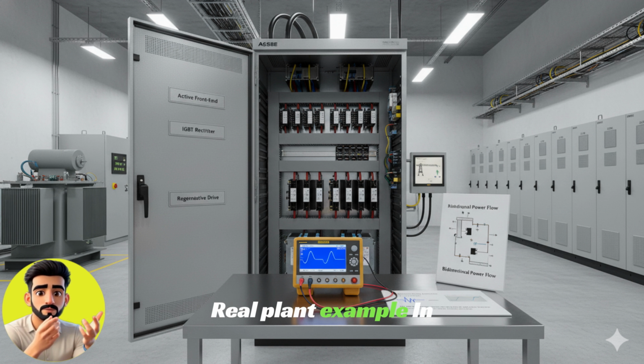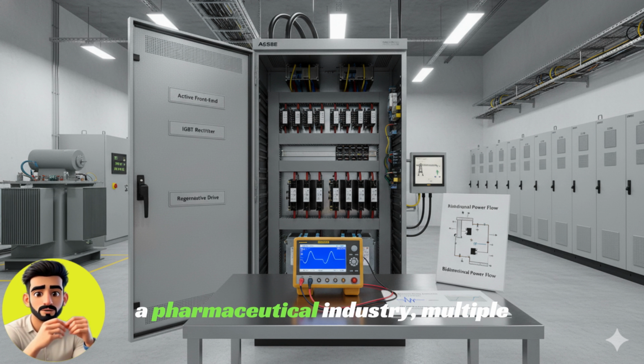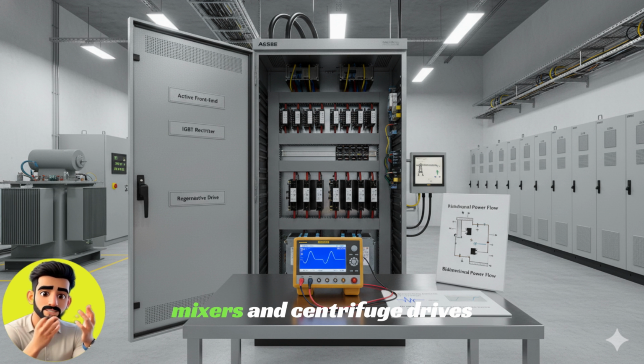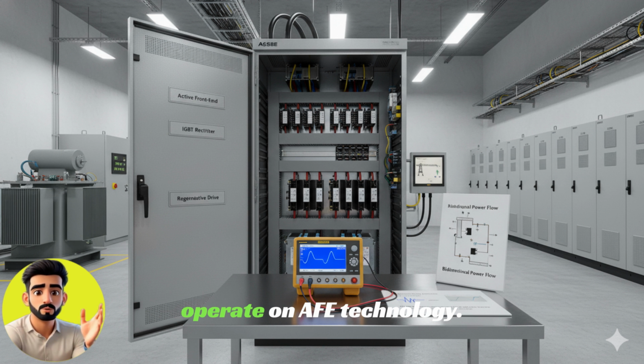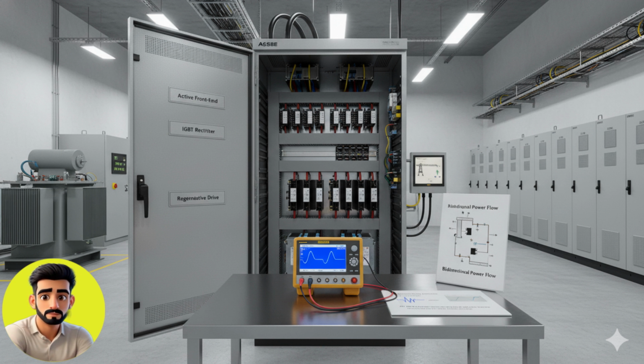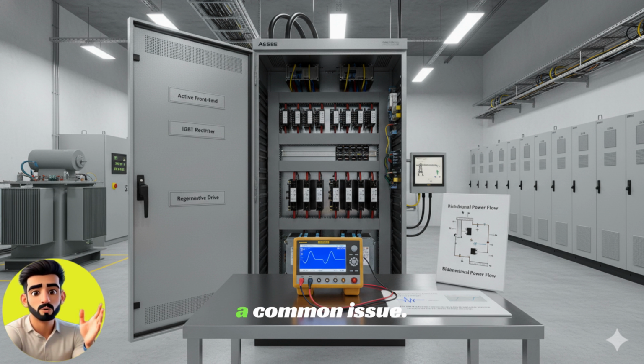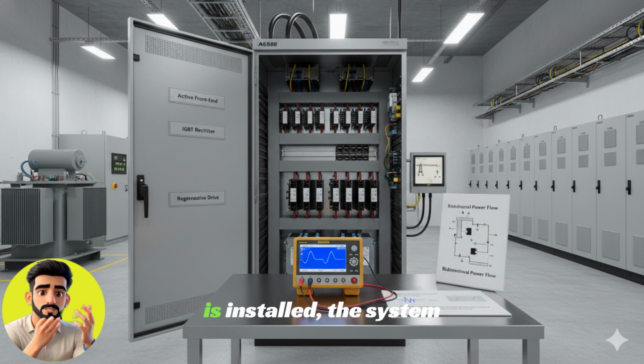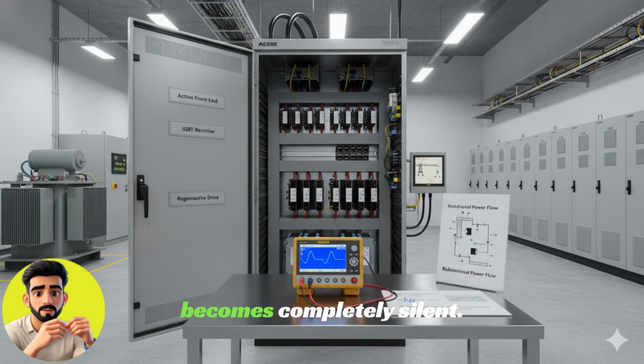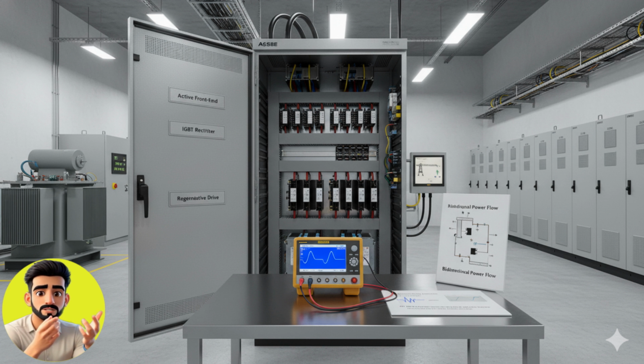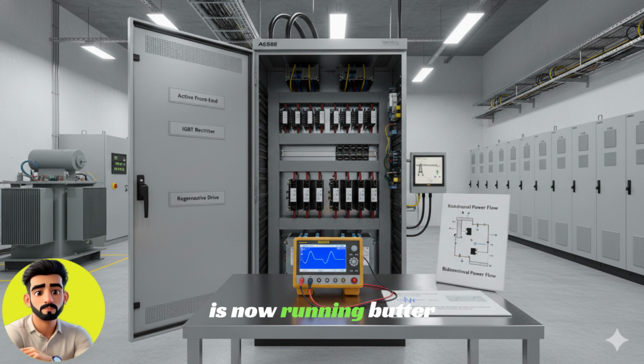Real plant example. In a pharmaceutical industry, multiple mixers and centrifuge drives operate on AFE technology. Initially, harmonics were high. The generator was unstable, and voltage flicker was a common issue. As soon as the AFE drive is installed, the system becomes completely silent. The generator becomes stable. Voltage flicker reduces to zero. And the operator actually said that the system is now running butter smooth.